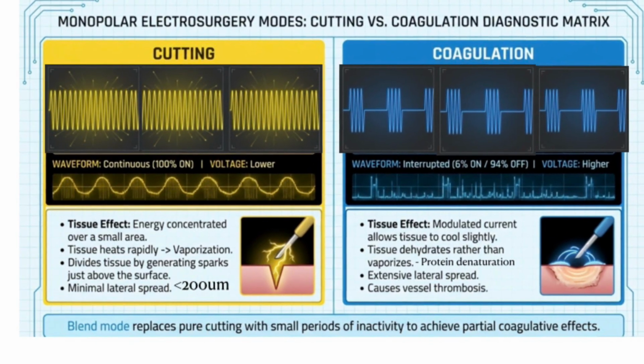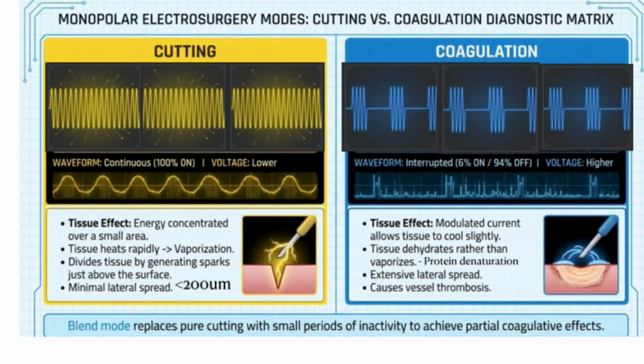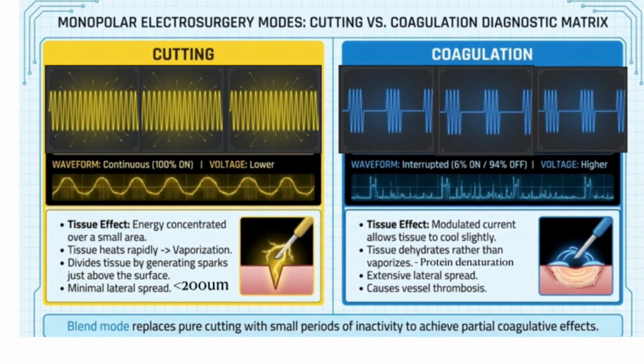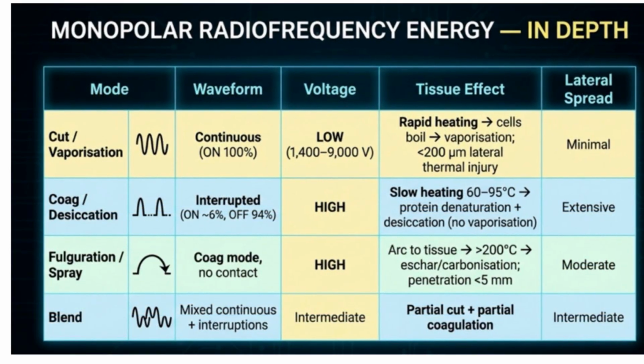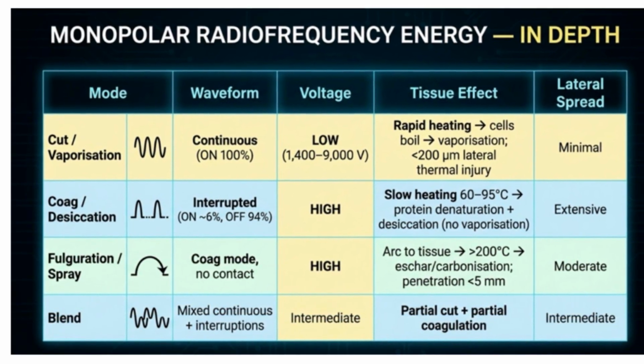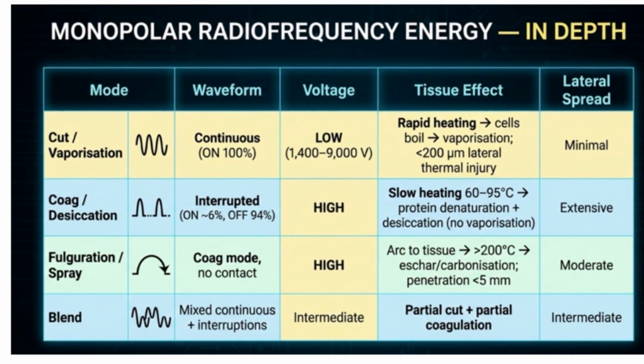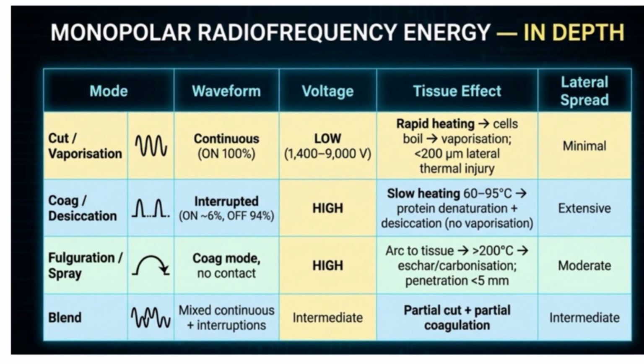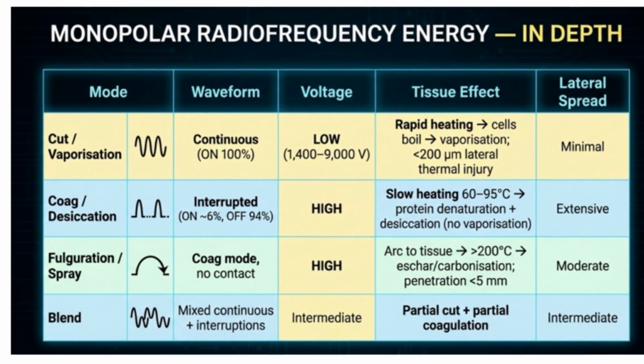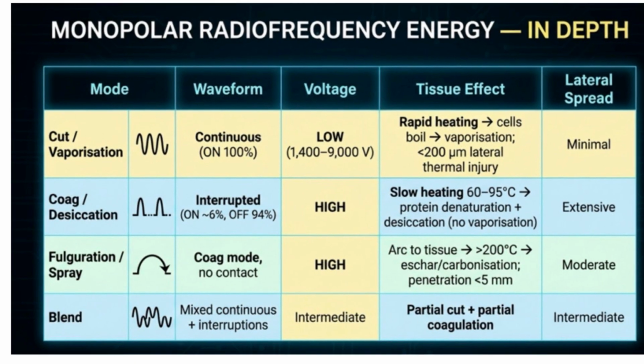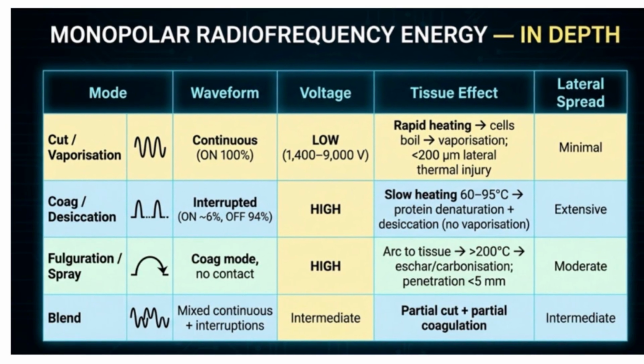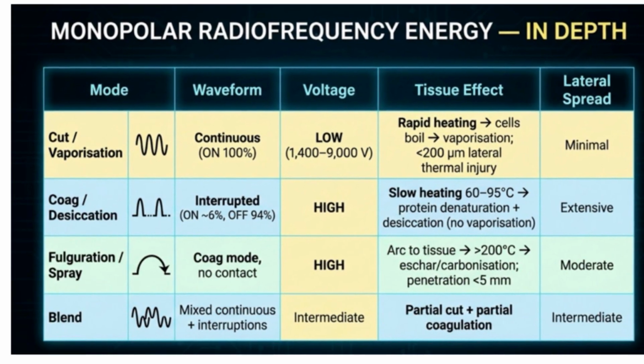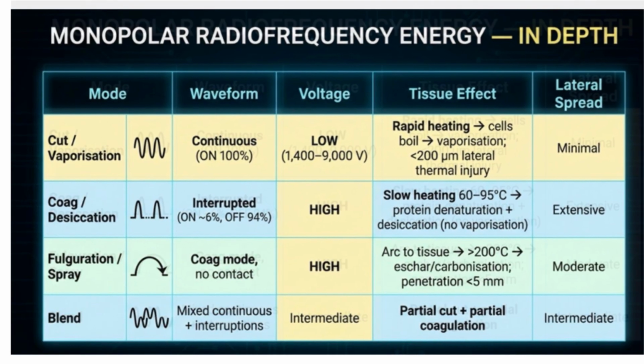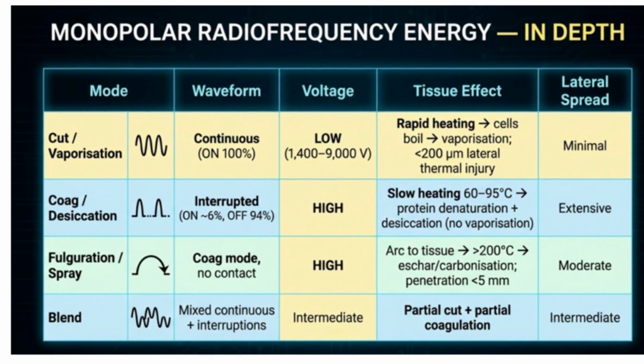The blend mode replaces pure cutting with small periods of inactivity to achieve partial coagulative effects. So the other forms of the monopolar radiofrequency energy source, the cut and coag, we have already discussed. The others are the fulguration or the spray mode, and the last one is the blend mode. Discussing all the modes together, cutting is a continuous, low voltage current of 1400 to 9000 volts. There is rapid heating causing vaporization, less lateral thermal injury spread, and the lateral spread is minimal.